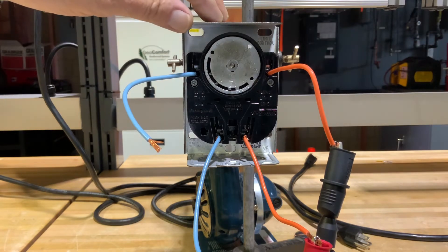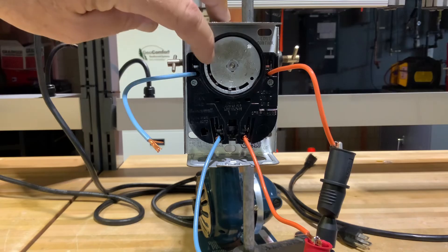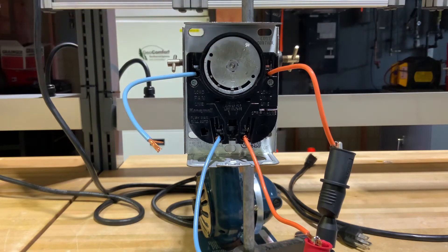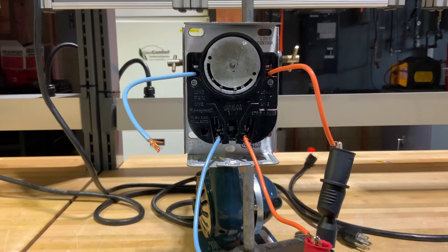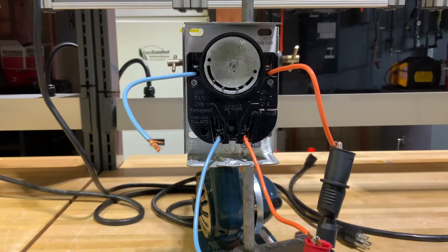You can see that thing is resetting itself, it's starting to cool off. Never, ever jump out a limit switch. It's a safety, it's there for a reason. It senses high temperature. If someone were to jumper that thing out, that creates a dangerous situation because you've just eliminated a safety.